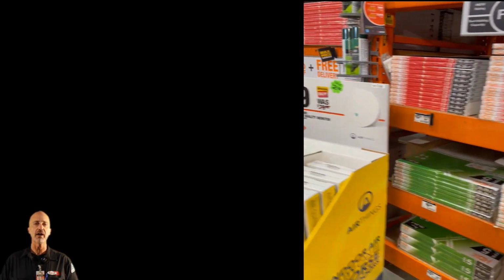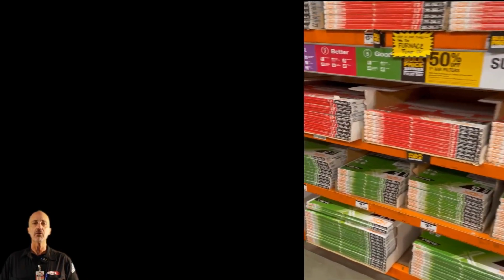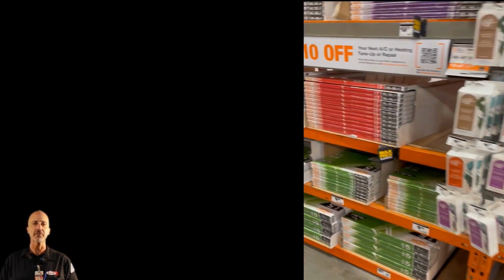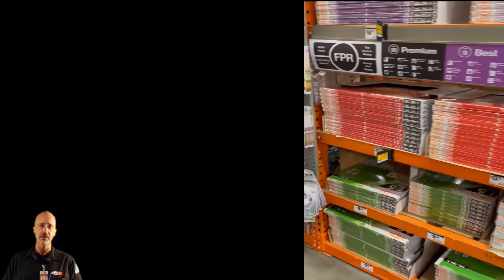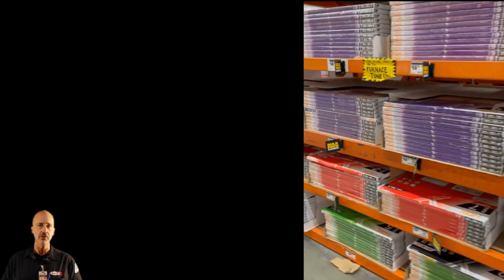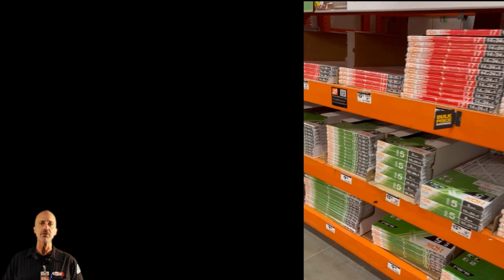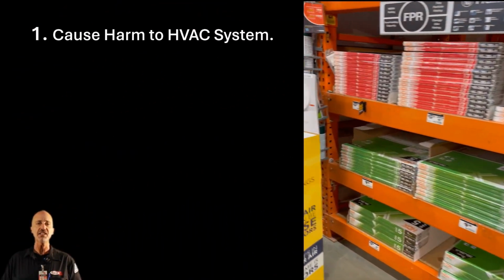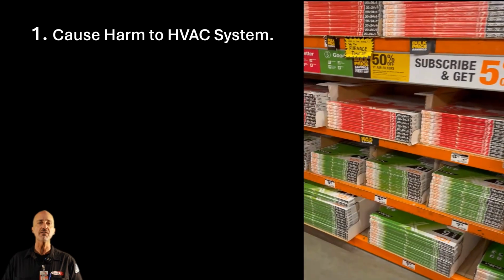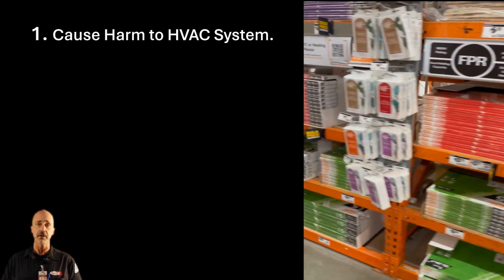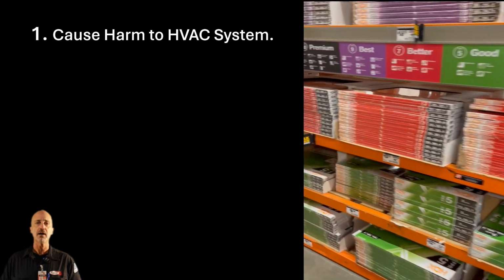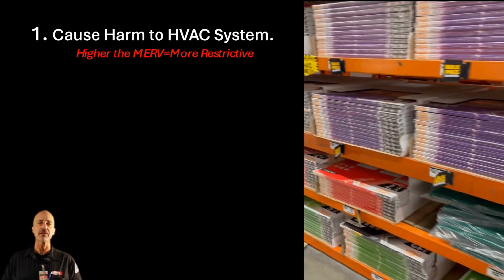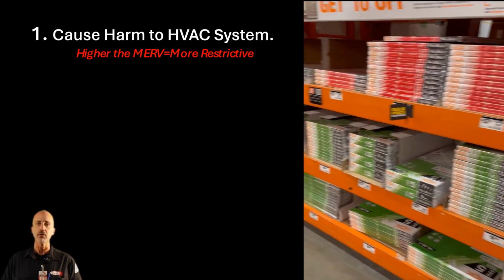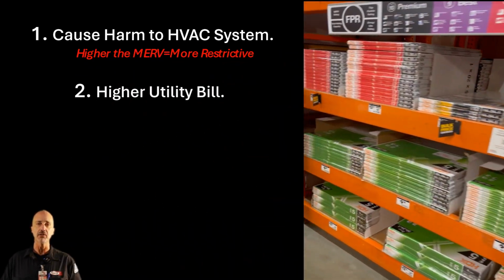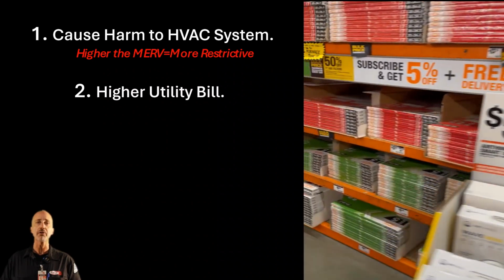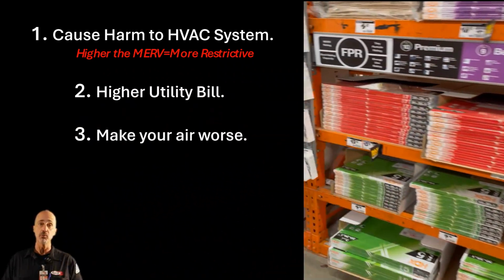When you walk down the filter aisle at your local store, you have a whole bunch of options, different filter colors, different claims and ratings. It can be confusing. So how do you know what filter is best for you and your system? First, we do not want to harm our HVAC system by installing too restrictive a filter in an attempt to have cleaner air. As a general rule, the higher the MERV rating, the more restrictive the filter. If you pick wrong, you could cause yourself a higher utility bill. What's more, the better air quality you think you are getting could actually be worse.